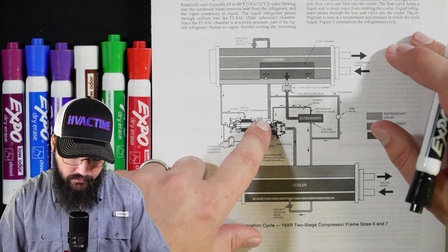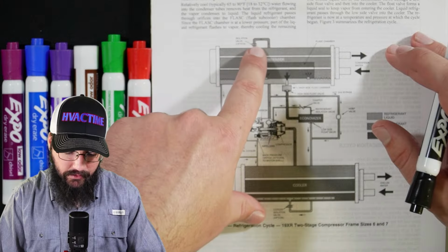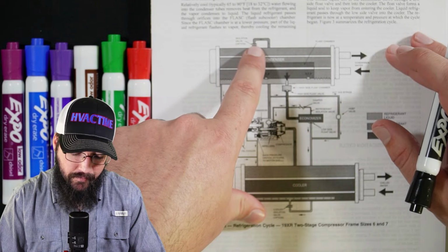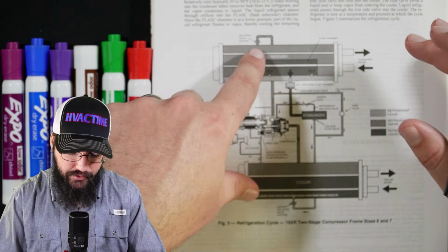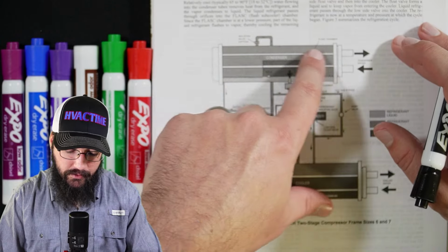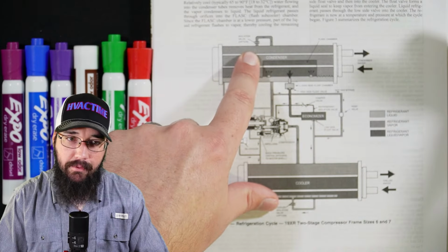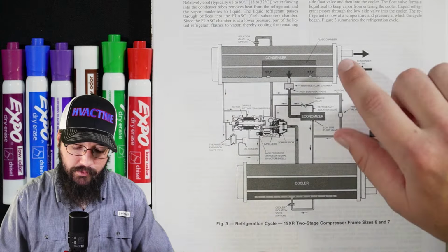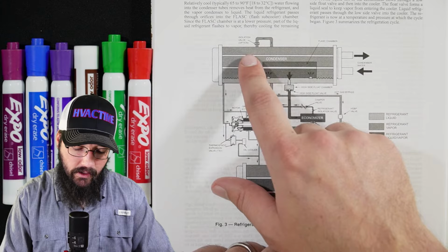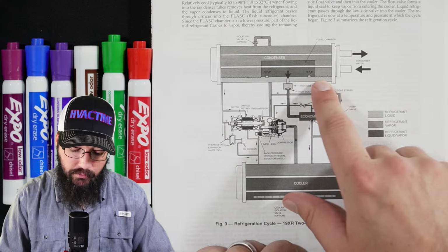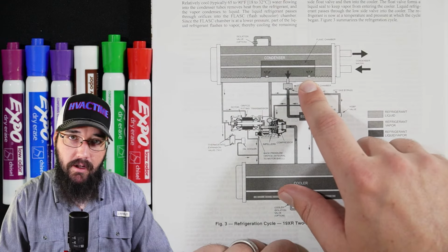So we come out of our discharge, coming into the top of our condenser barrel. This then pushes that discharge gas down into the barrel itself. Condensing happens, right? We have condenser water tubes in here that we're flowing across, and then that removes our heat. We start to build a column of liquid here in the bottom.